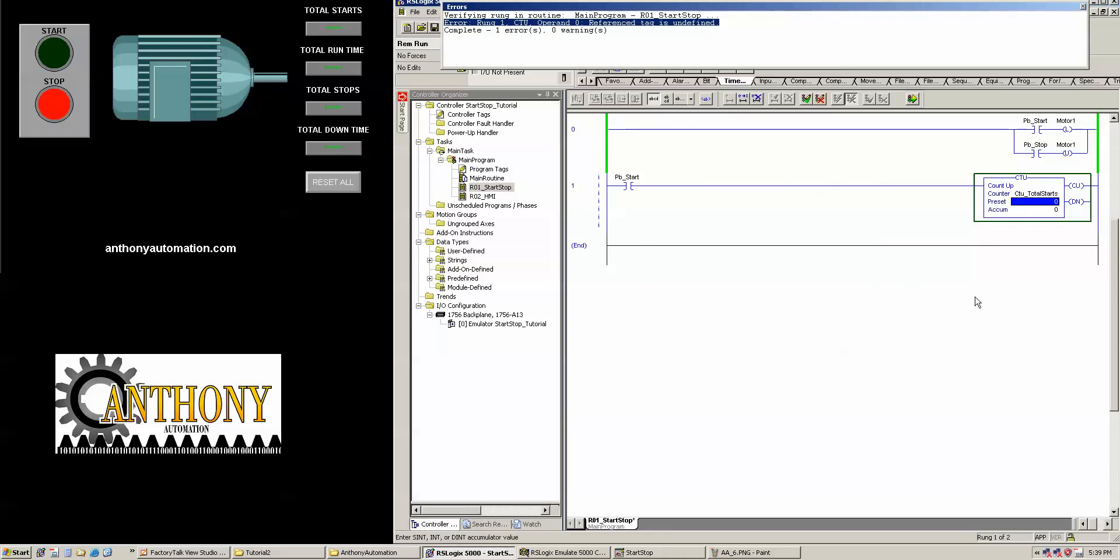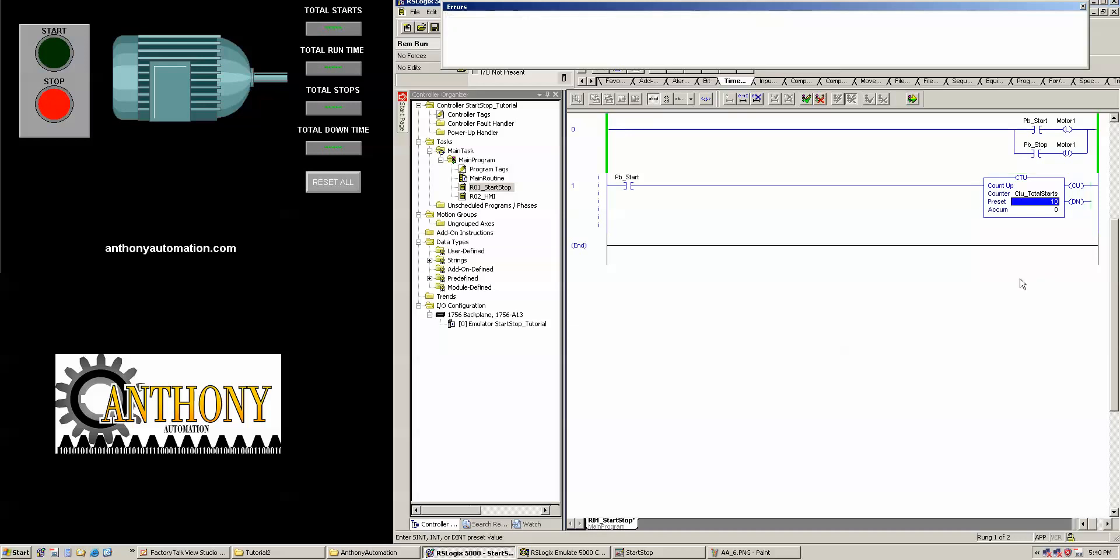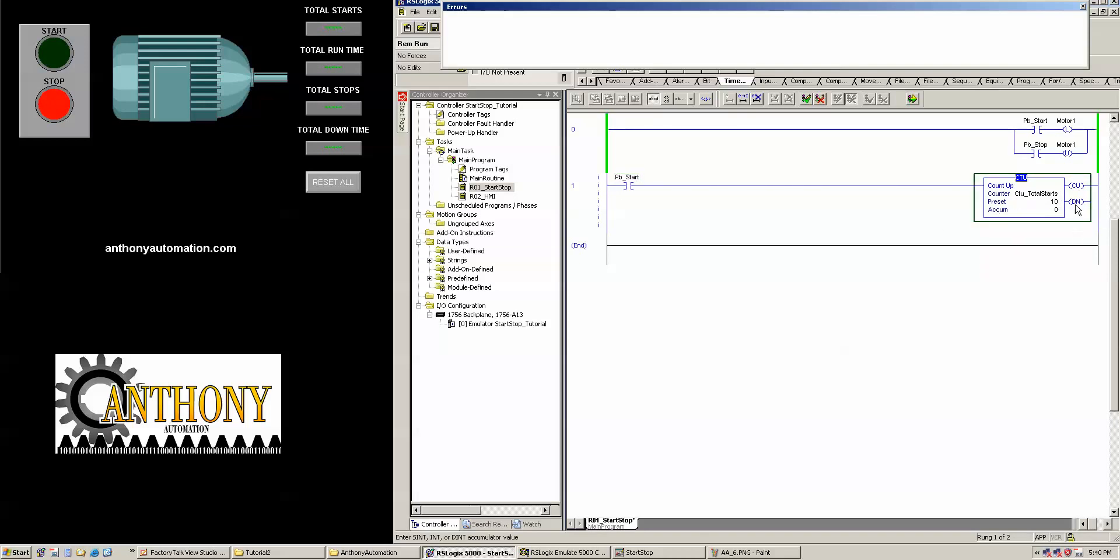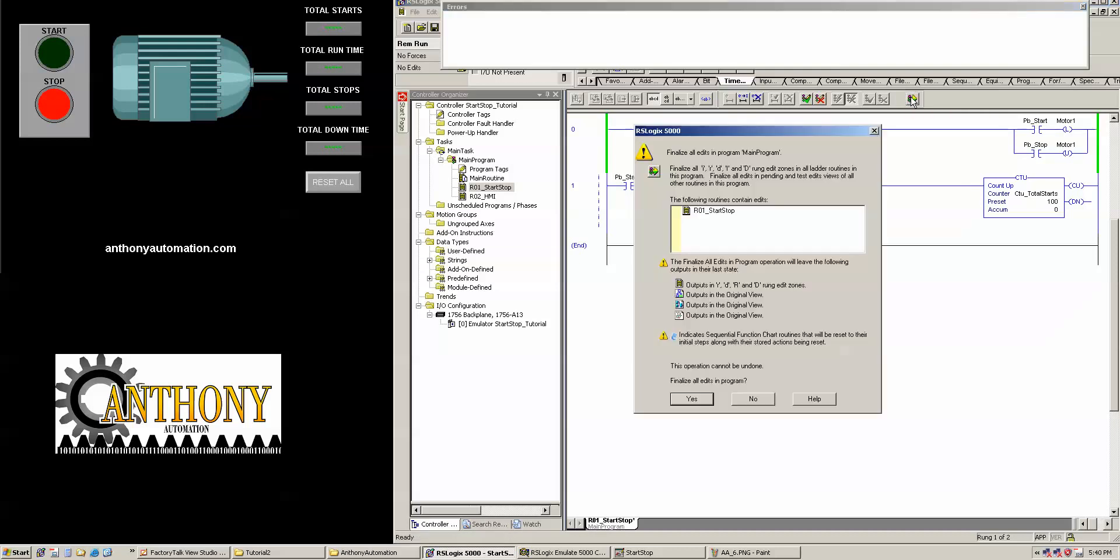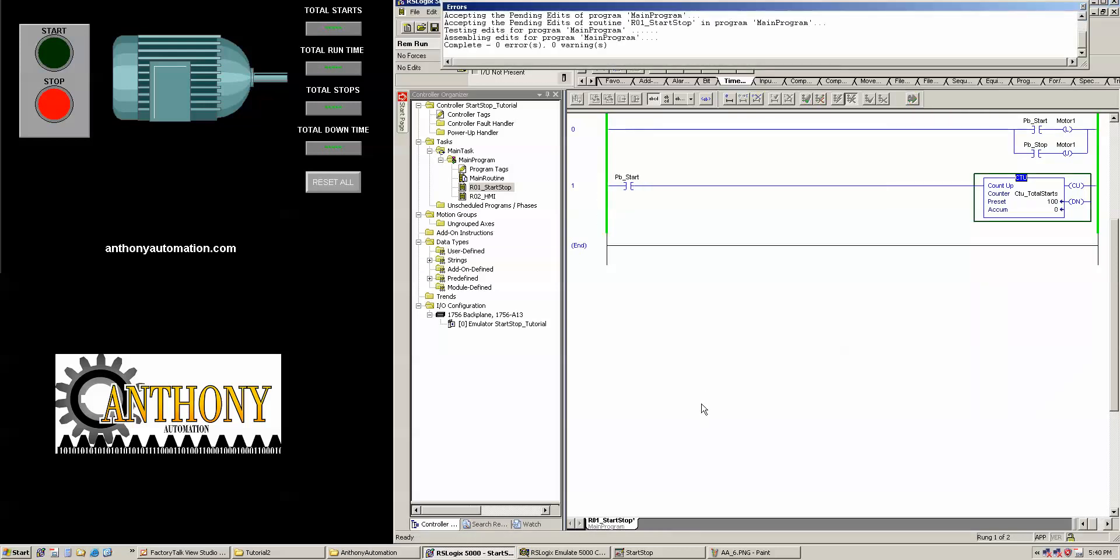And then I'm going to have to give it a preset value. Preset value is the value that you are going to set in there before the counter is done. See these two bits over here. The CU is counting up, meaning the counter is active, and the DN is done, meaning it has reached your preset value. So, if I set my preset value to 10, when this start button is pressed 10 times, that counter will be done. Every time the start button is pressed, during the time that this is high, the CU bit will be high. And you can use these, and we will probably use them. We're going to make this a little higher, though, because we're not ready for using the done bits yet.